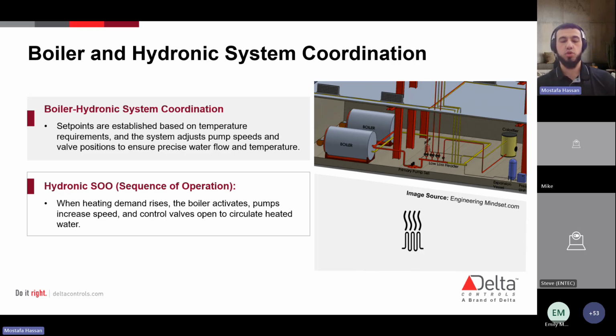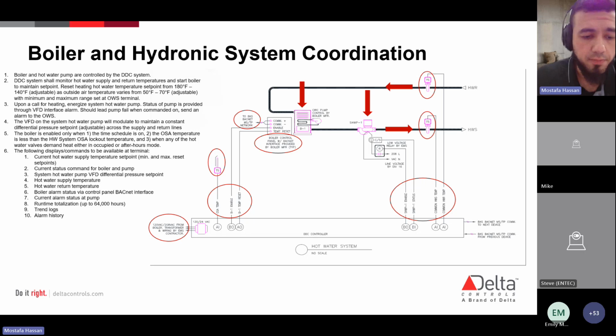There was your hot water supply system that we're looking at, the boiler. And again, Emily mentioned this is your system that's going to be providing heating throughout your building, and it works in tandem with a lot of other equipment. In this scenario, we'll get right into the sequence here. So this sequence will actually be built on the screen as I go along.